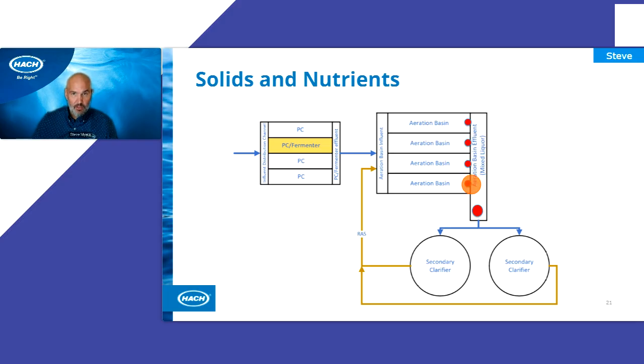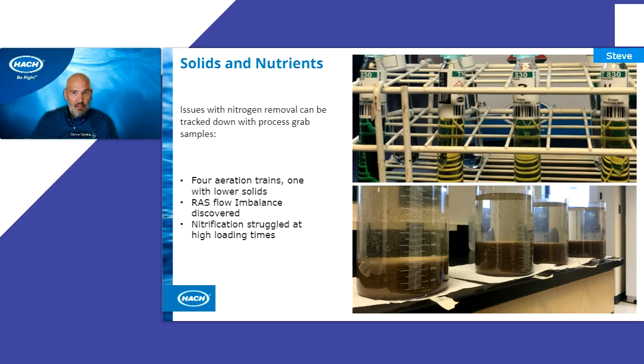So they went in these smaller circles here. These will represent essentially where they did some grab samples to take a look and see what's going on in our process. Now this slide, a little bit to unpack here, but on the top we have vials, some of our test tube vials for ammonia measurements. The yellow represents a low amount of ammonia in the water, and green over here represents a higher amount of ammonia in the water. And these all represent each one of those 4 aeration basins. And down below, each of these settleometers correlate to one of the vials above. So we can see them going from left to right.